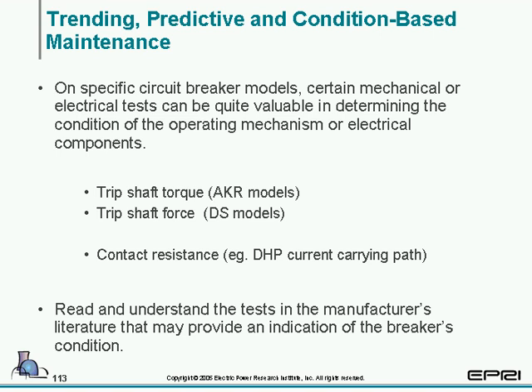Let's see, continuing on with trending and predictive condition-based maintenance. On certain circuit breaker models, there are mechanical and or electrical tests that can be quite valuable in determining the condition of the operating mechanism or electrical components. Mechanical tests I'm talking about are trip shaft torque and trip shaft force. Now, Gene is going to cover these next week in a lot more detail, but basically these are just mechanical tests that, again, it's breaker specific. It may not be able to be performed on your breakers, but a lot of breakers you can do this. Certain mechanical tests will tell you somewhat the condition of your mechanism.